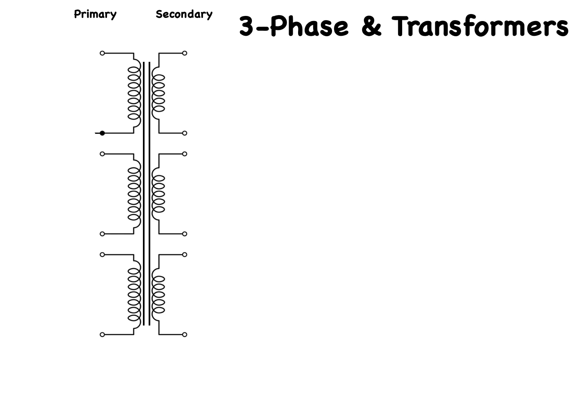I am now going to connect the bottom side of each winding on the primary side of the transformer and ground that connection, designating it as neutral or N. The top side of the winding I am going to connect to a balanced three-phase power system designated R (red), W (white), and B (blue). This is known as a Y connection, designated as such on drawings and nameplate data as shown here. The fact that the neutral is grounded is indicated with a grounding symbol coming from the center point of the Y.